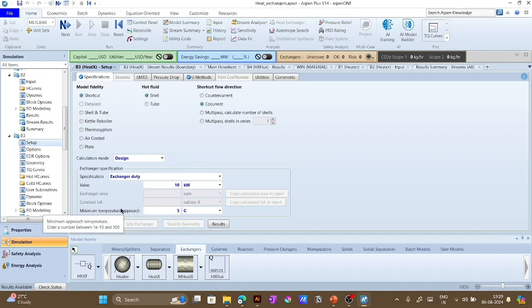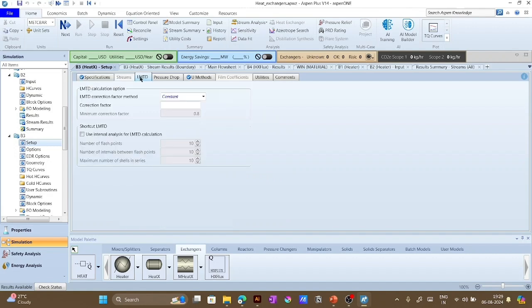Now, this is the basic shortcut design we want to do. In this shortcut design, you can further specify various parameters, like LMTD. Generally, designers use correlations to account for factors such as fouling or effective heat transfer, so you can provide various correction factors to the LMTD value—calculating the LMTD correlation for exchangers based on geometry.